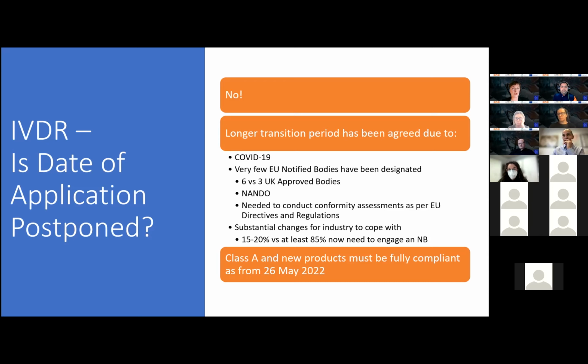If you want to see which notified bodies cover what and what they're designated under, then search for NANDO and you can see a listing on there. So notified bodies, their role is they conduct the conformity assessments against the EU directives and regulations. So they review your technical documentation and of course your quality management system for certification purposes. There's huge changes, and that's again why they've agreed on a transition period. And as I mentioned already, at least 85% of diagnostic companies will now need to engage with a notified body. So it's a complete culture change. And you know, this industry is far more regulated now than it was under the old directive. So in Class A, the low risk products and any new products coming onto the European market will need to be compliant as from the 26th of May 2022, which is the date of application.